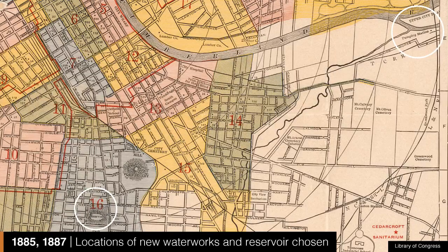So we adopted all the recommendations. We relocated Browns Creek, put in a new pumping station connected to a 36-inch cast iron main that pumped it to 8th Avenue, built that two-cell reservoir on top of Kirkpatrick Hill, which actually wasn't his initial recommendation, and then allowed for settling in the first cell and distribution in the second cell.